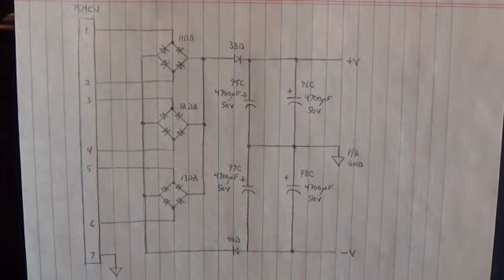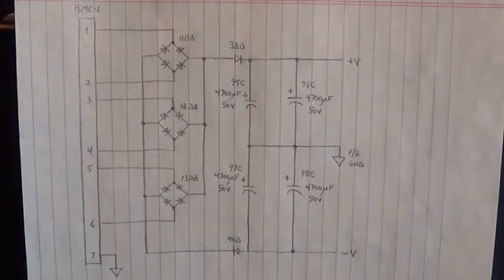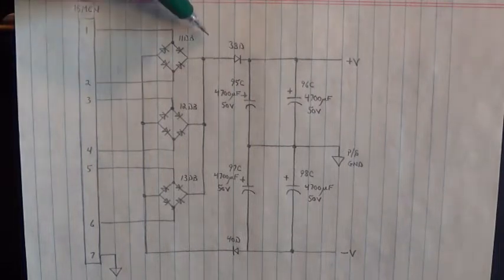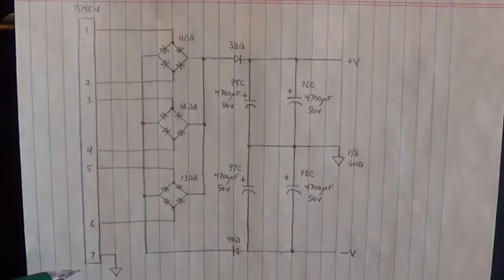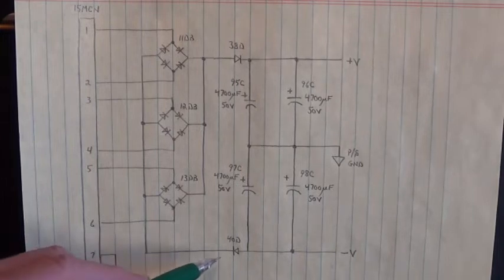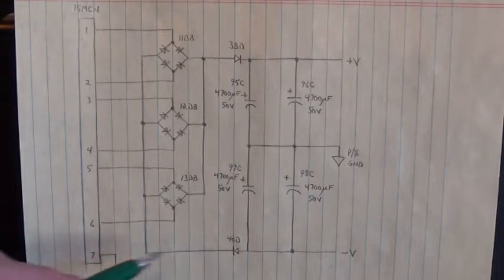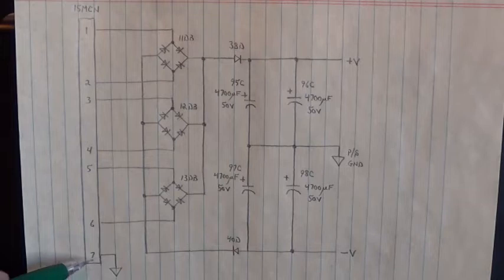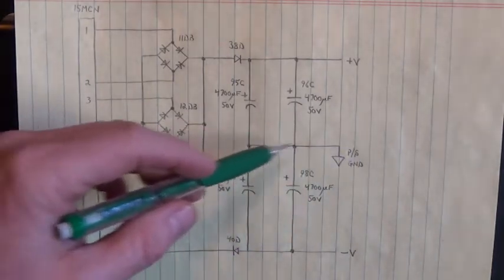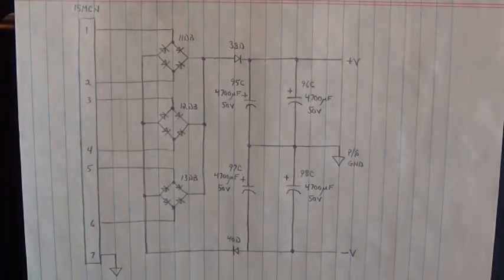In order for me to power up this board without having to dig that transformer out of the belly of that drive, I put plus 24 volts DC on the anode of this rectifier right here from an external power supply with the ground connected to pin 7. The external power supply ground is connected to pin 7. Secondly, I put a negative 24 volts DC on the cathode of this diode right here, referenced to this ground right here to make a plus and a minus voltage with ground in the middle. And that powered up that firing board.